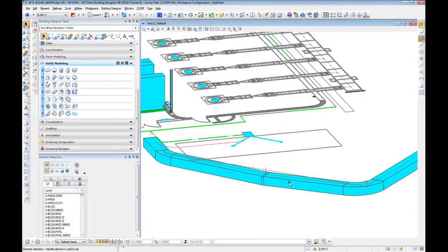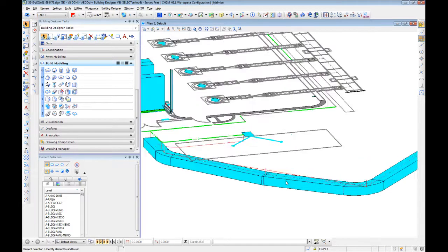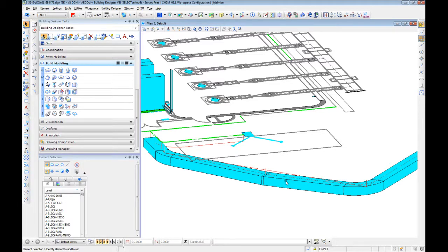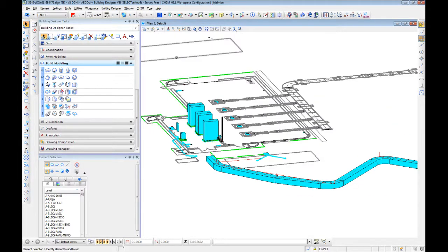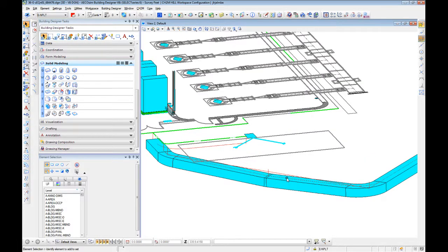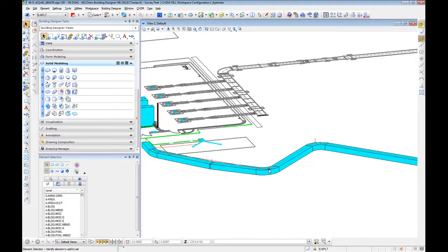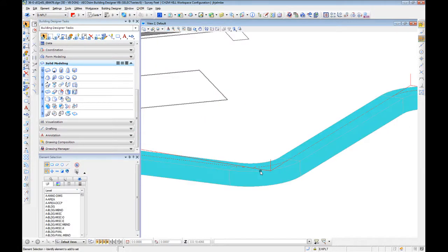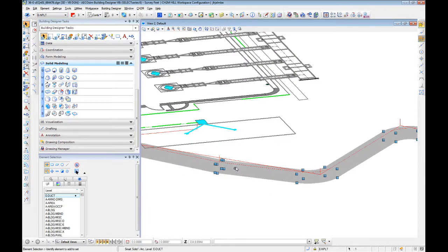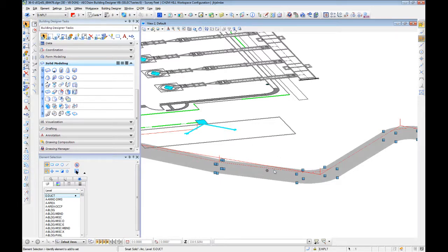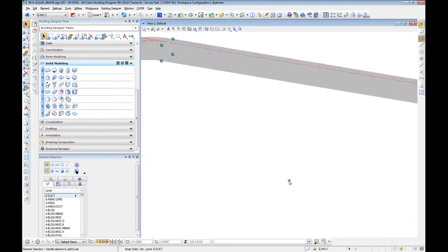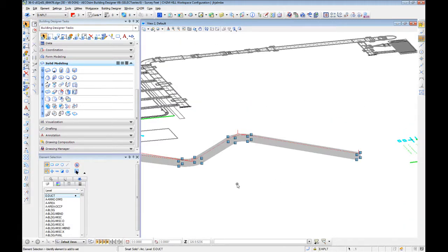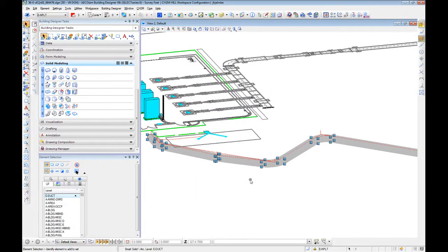This is an iterative process. I rarely get it right the first time through. I'll grab all the conflicts I can see, get everything set, and then turn everything off and on one at a time just to make sure that everything I should be avoiding is avoided and that I'm not missing something, like there's a massive ditch here that I didn't see initially, that my duct bank isn't showing through the triangles for the surface.